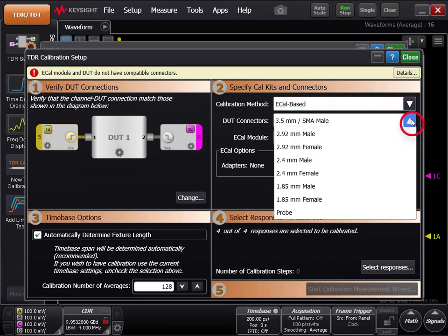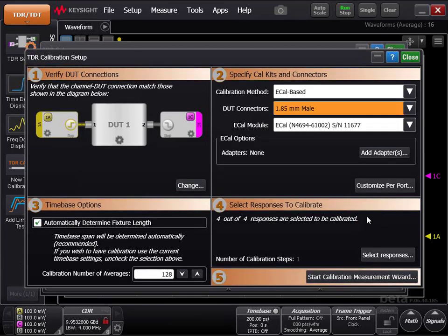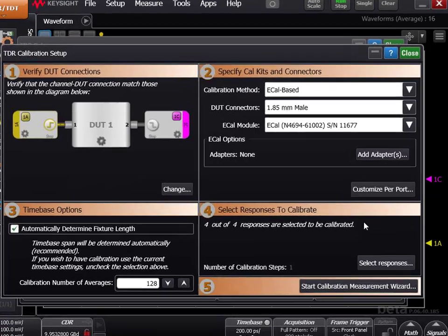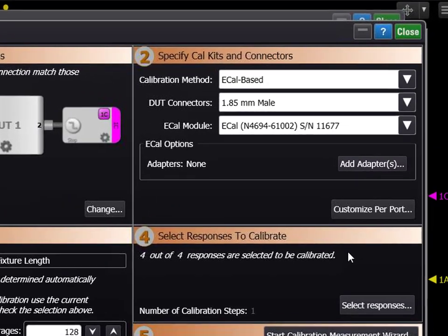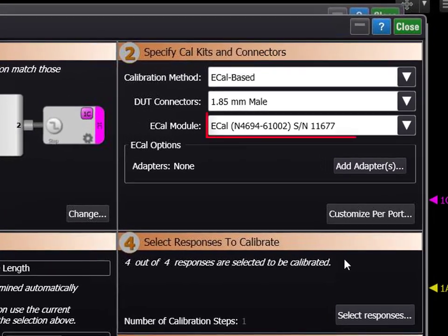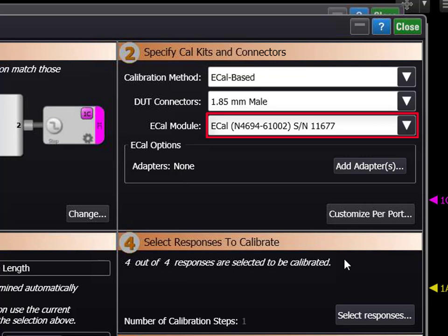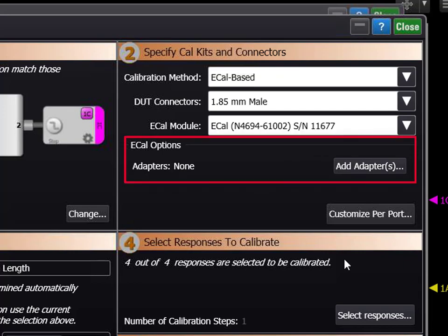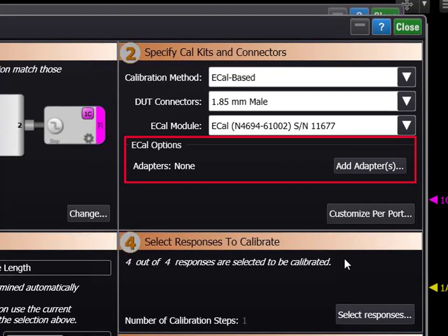Under DUT connectors, specify the connectors your DUT has. In this case, it's 1.85mm male. The ECAL module should already be selected. If you have multiple ECAL modules plugged in, make sure you have the correct one selected for your calibration. For now, leave the ECAL options empty.